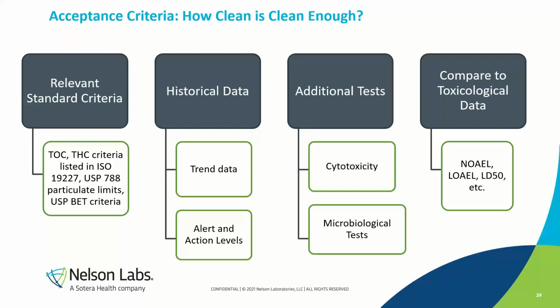ISO 19227, which published in 2018, actually put numbers on TOC and THC as starting points, 0.5 milligrams per orthopedic implant, granted. USP 788 particulates does offer limits for water for injectables. It's not designed for medical devices, but it's sort of the best we have available. And the argument is, if it's conservative enough for water for injectable that can be introduced to circulatory systems, then it's conservative enough for a medical device, or it's more conservative.